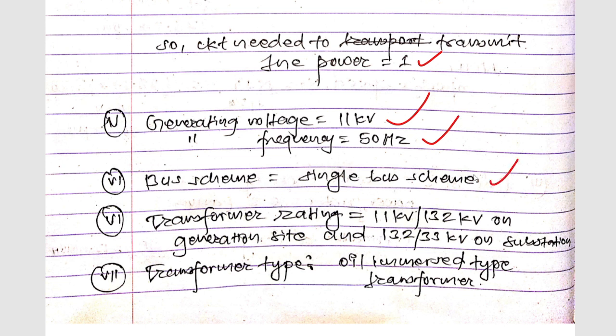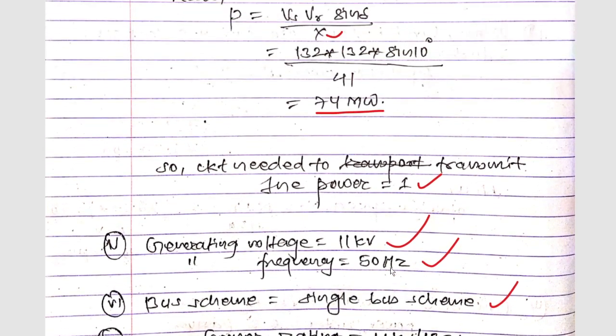Generating frequency will be 50 Hz. The bus scheme will use single bus scheme. Transformer rating will be 11 kV / 132 kV on the generation side, and at the substation 132/33 kV. The transformer type will be oil immersed type transformers. These were all for the design part.